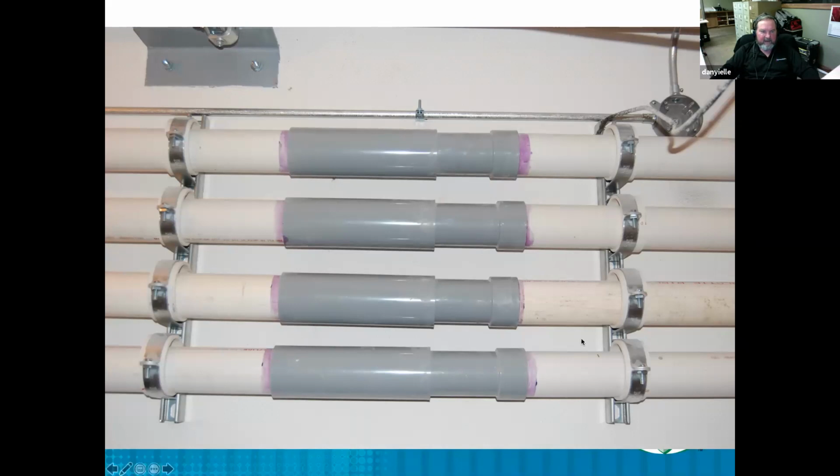So you can see that we've got glides set up here, and on the far ends of the system, we've got it locked. So basically we're sending the growth and the expansion and contraction potential into these joints. And as a part of this, I required him to put a water sensor on the floor below these so that if they ever started leaking condensation, we would be aware that we had a seal failure, which not only is going to lose condensation, it could also lose flue gases.